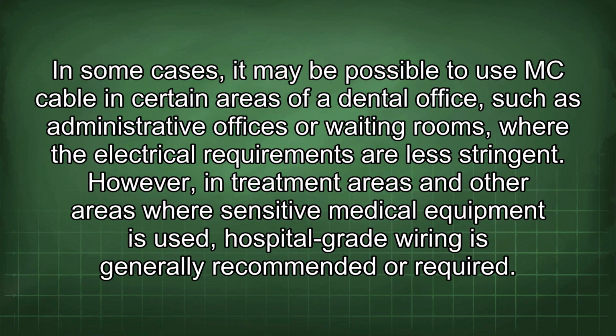In some cases, it may be possible to use MC cable in certain areas of a dental office, such as administrative offices or waiting rooms, where the electrical requirements are less stringent. However, in treatment areas and other areas where sensitive medical equipment is used, hospital-grade wiring is generally recommended or required.